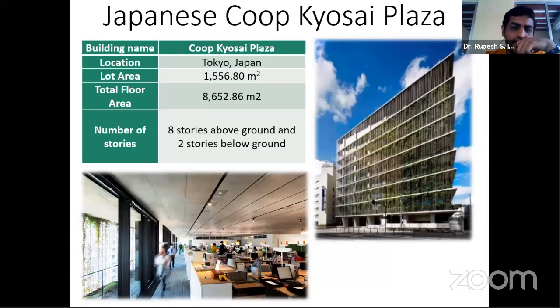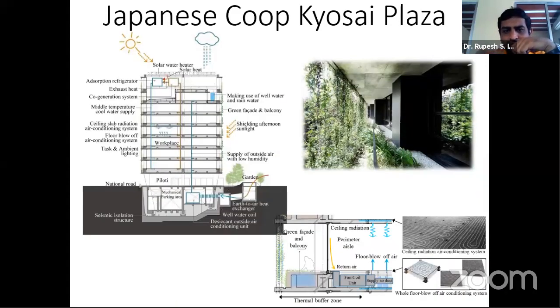Then yes, this is one more. We were a part of this in Tokyo. It had a total floor area of close to 1 lakh square feet or 8,600 square meters, 8 stories above the ground and 2 basements. It is again a nearly net zero building. An adsorption refrigeration system was used because there was heat made available, linked to a solar panel plant. And then there was also an earth to air heat exchanger, and a desiccant unit. Again, radiant cooling is a part of this project.